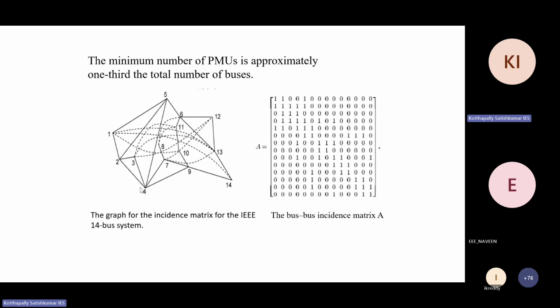Because I placed the PMU at node number 4, I know the voltage at 4, and I also know the currents flowing between 2 and 4, 3 and 4, and 4 and 9, because we measure the currents in these lines, and you already know the line impedance. Using this voltage and the impedance drop in the line, you can calculate the voltage at 2, 3, 7, 5 and 9. So the nodes directly connected with 4 are 2, 3, 5, 7, 9. There is really no need to put a PMU at node 2, 3, 7 or 9, because the PMU placed at 4 automatically gives the voltage at 2, 3, 5, 7, 9.